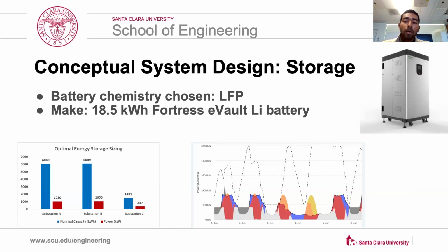Delving into the REopt analysis, we summed up the 15-minute kilowatt hour consumption data provided to us in the simulate campus tab in REopt, and in the resilience tab inputted meeting our objective of 50% of the critical loads for 4-hour durations during grid outages.